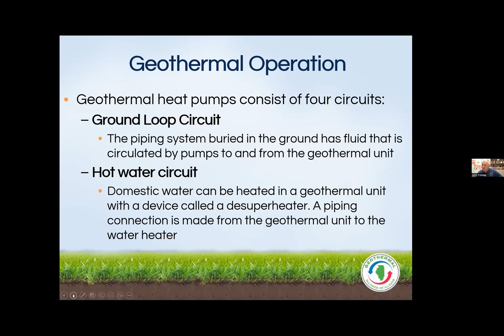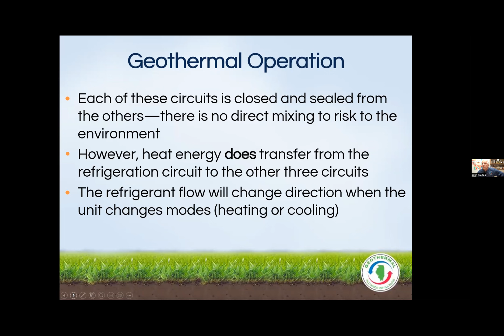But every geothermal system has the ability to supplement hot water needs, if not make all of the hot water needs. This is also an important slide because it's important to remember that all 4 of these circuits are sealed and closed from each other. In other words, the refrigerant within my geo unit doesn't intermingle or mix with the fluid in my closed loop field. And neither of those intermingle with the desuperheater that's supplementing my hot water needs. It's important that all the circuits work together and cooperate with one another, but they don't transfer any fluids or air between themselves. They merely work together.